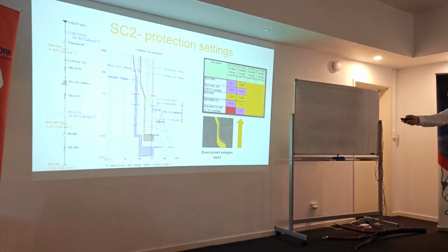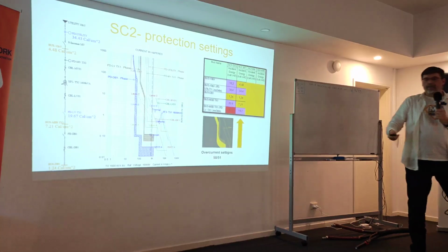So I can keep clicking like this if you want, yeah? So you can see the difference. I improved the selectivity and changed the setting, improving the selectivity and the results at the same time, which is not always possible, yeah? Selectivity is a compromise, or the grading of the protection of the way. So it's a compromise for the time. So you want to have a nice separation time between the breakers or the relays, but then you go to the higher times. Yeah? The higher times mean more energy most of the time.